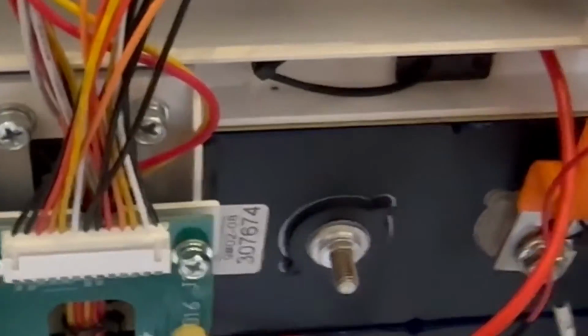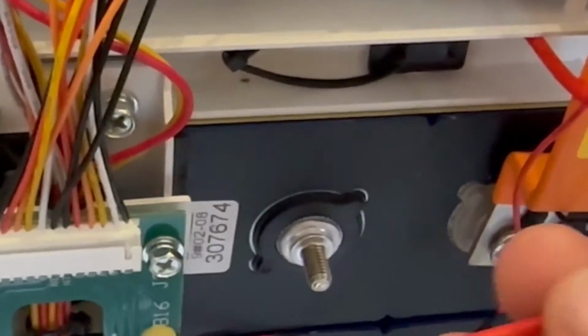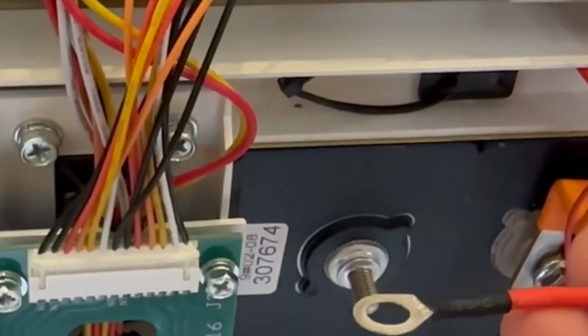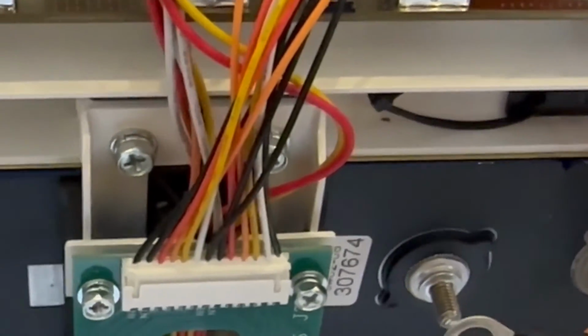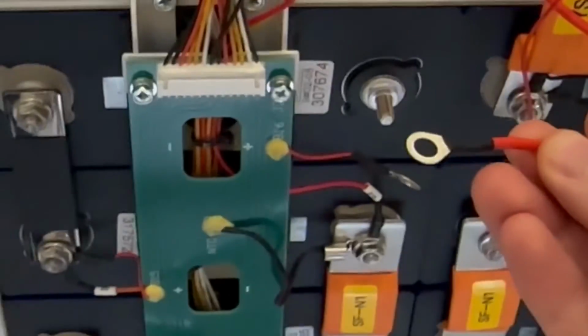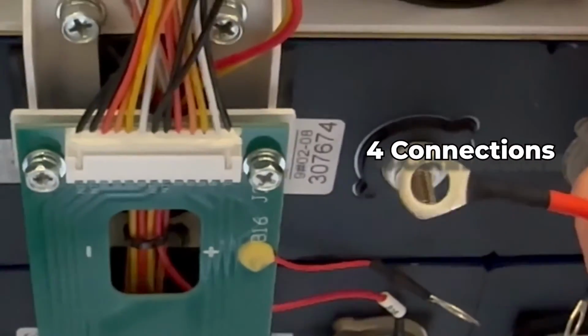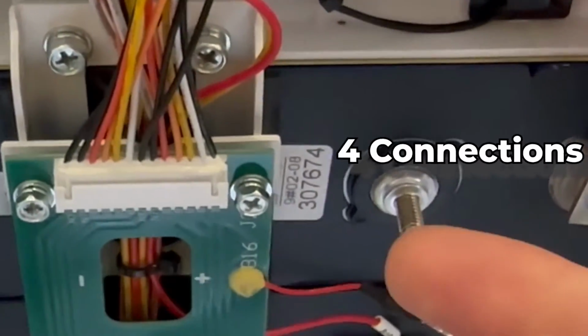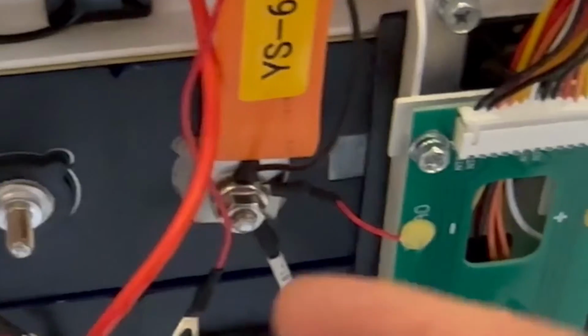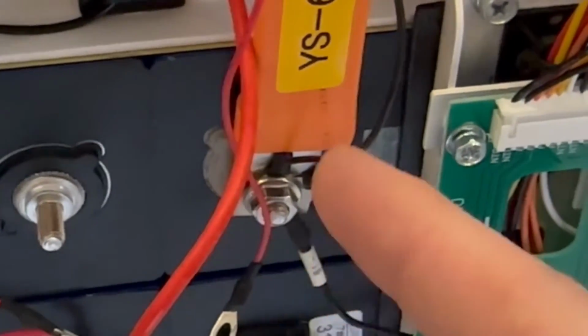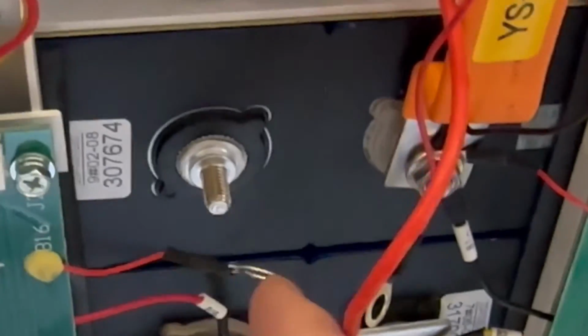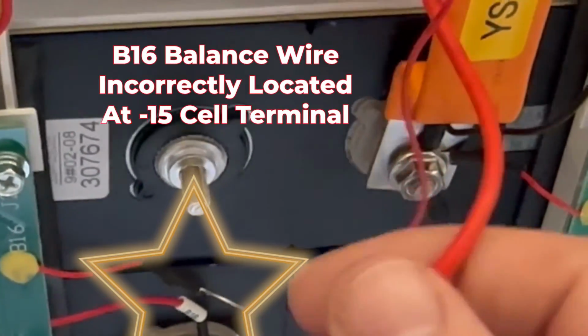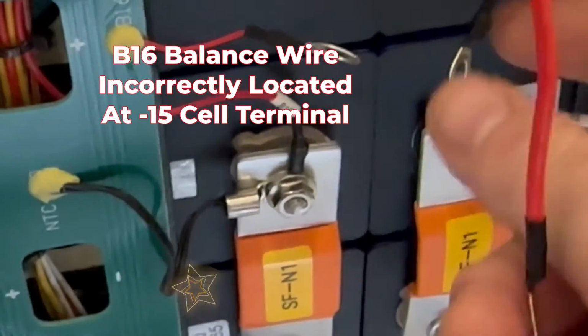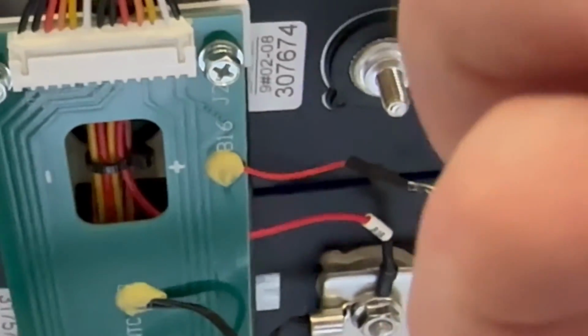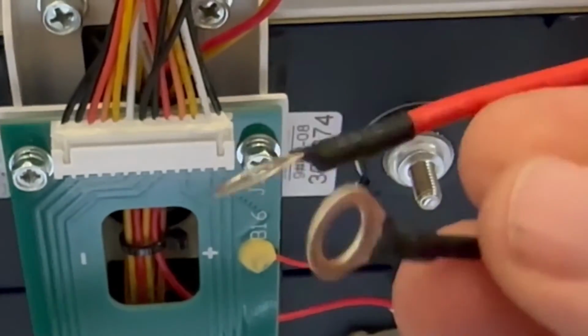This B plus cable, I've run it under the BMS, or rather under the shelf, and this is it here. It's a slightly thicker gauge than the rest of the cables. That connects to the positive terminal on cell 16. So you'll have 3 connections plus the bus bar connecting to the positive on cell 16, and you'll also have 3 connections connecting to the negative terminal on cell number 1. So you'll have your voltage check, your battery plus in this case, and that power connection that runs back up to your active balancer.